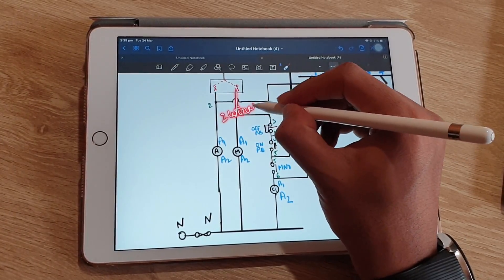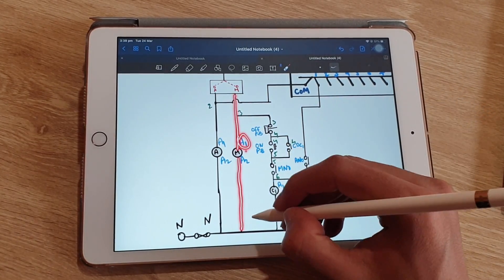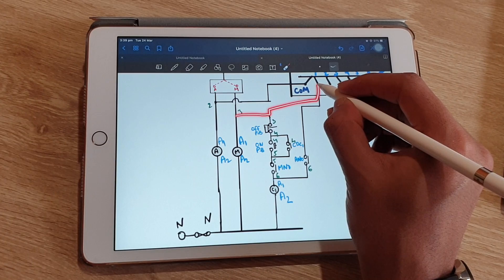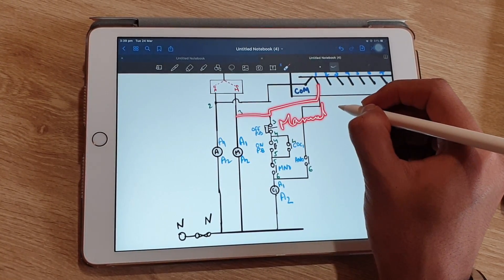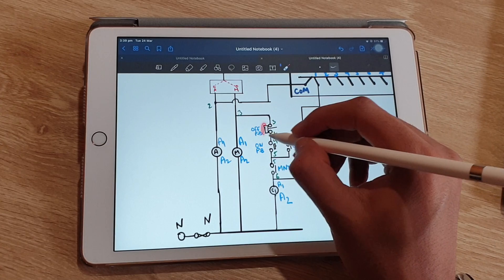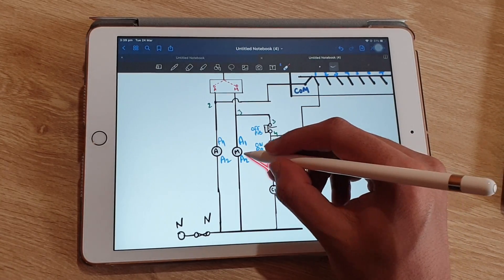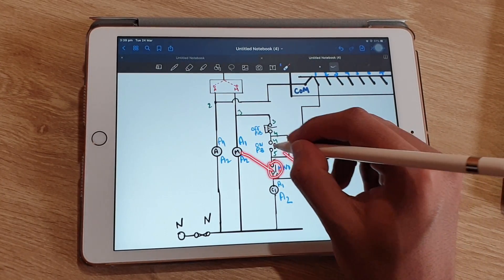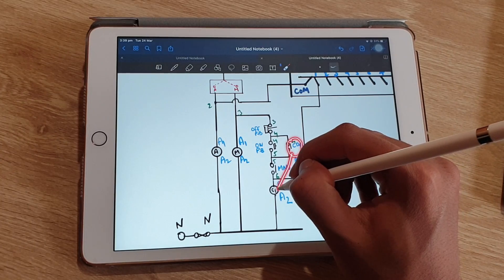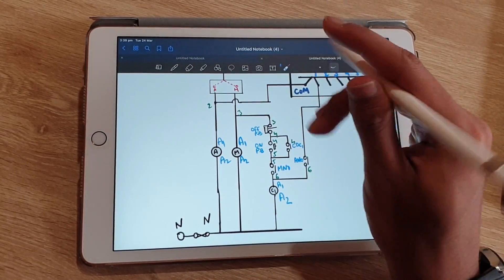From the manual terminal of the auto-manual selector switch, two wires are taken out: one wire is connected to manual contactor A1, and from A2 of this manual contactor it is connected to neutral. Another wire from this manual terminal is not connected directly to the APFC relay but is connected via the off push button, on push button, and the NO contacts of all the contactors. So from terminal three it is connected to the off push button, on push button, and NO of CDC — this is the NO of the manual contactor and the NO of the auto contactor.